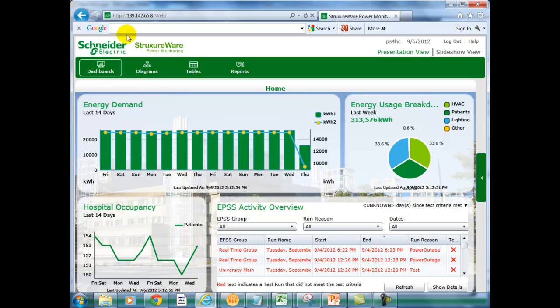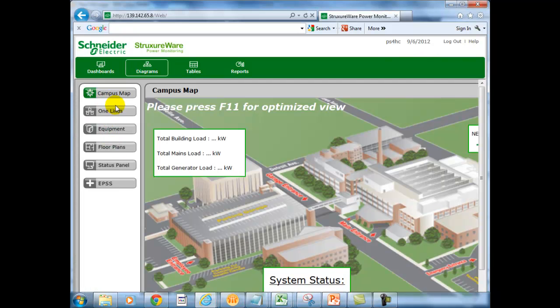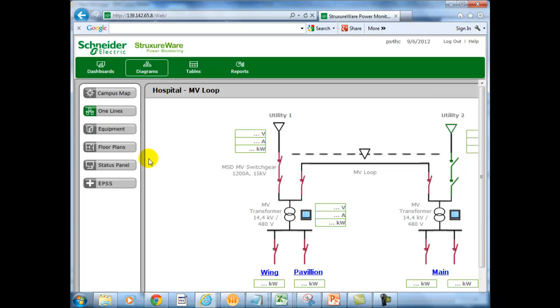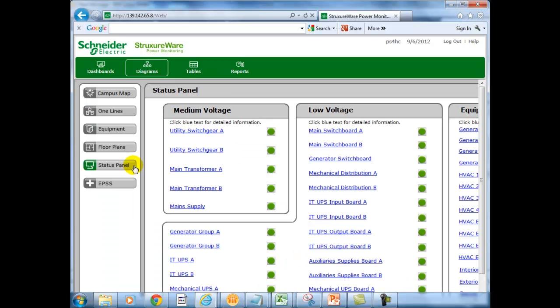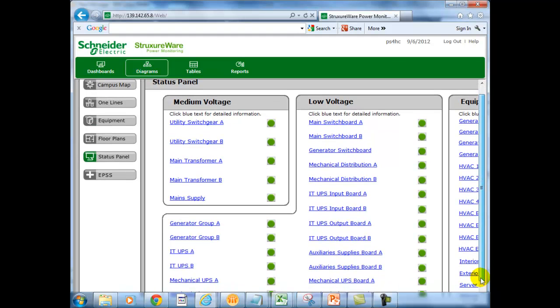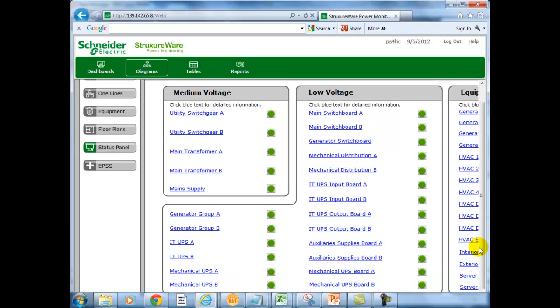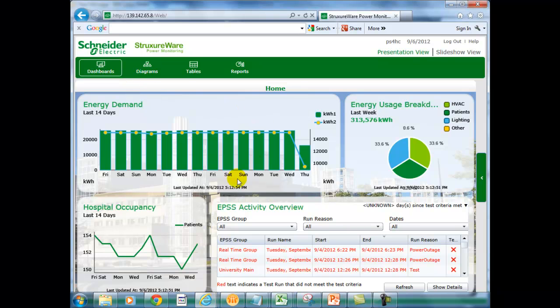Let's do a quick walkthrough. So here's a 2 megawatt healthcare facility. You would see all the typical equipment that you can expect to see in a facility of this type: medium voltage gear, low voltage gear, some HVAC equipment, UPSs, etc. At the dashboard level, you can see we have the standard energy dashboards, but in addition, we have an EPSS activity gadget which summarizes an aggregated view of all the generator tests that have happened in the recent past, with a quick fail pass indication as well.